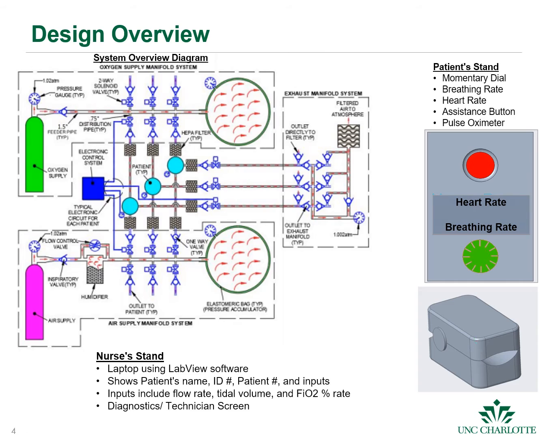Looking at the overall view, the oxygen and air supply will both be controlled by solenoid valves. They will go through a HEPA filter and combine before then going to the patient. When the patient breathes out with the help of another solenoid valve, the exhaust will go through a HEPA filter and release into the atmosphere.